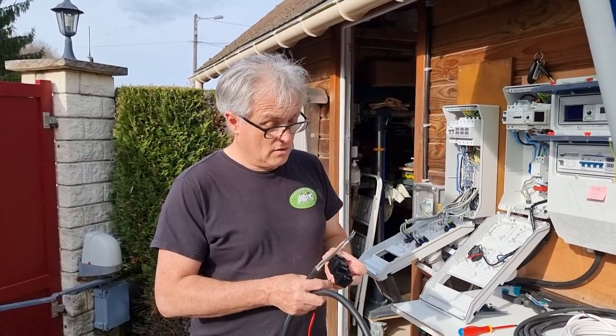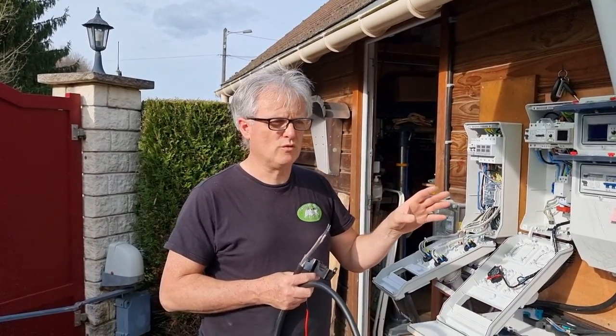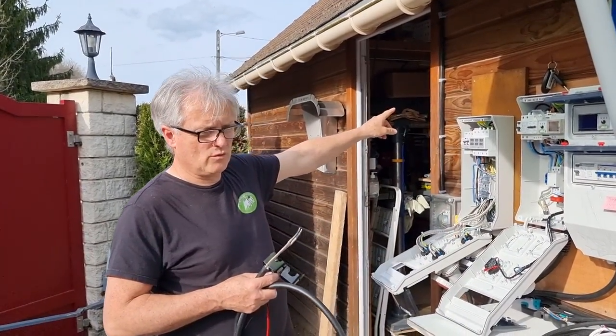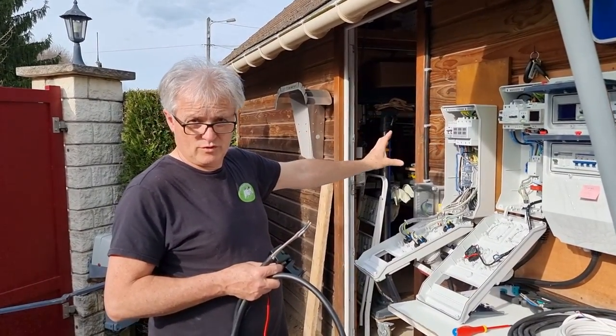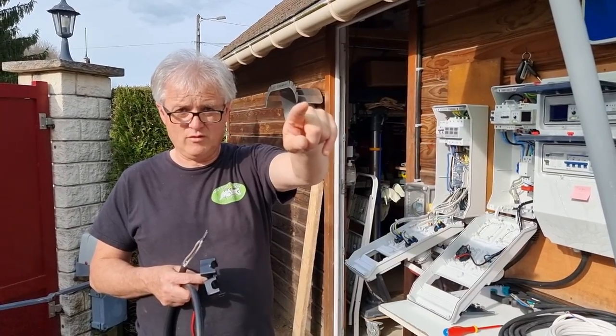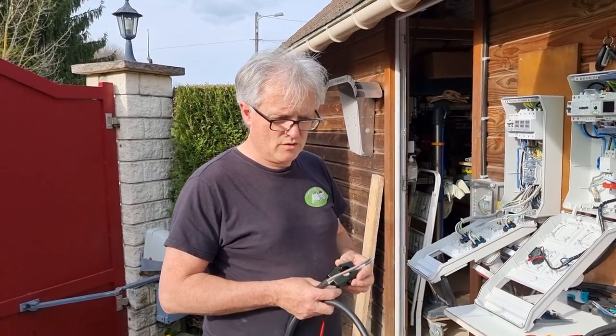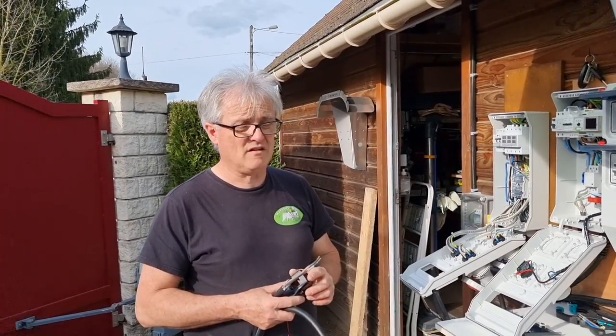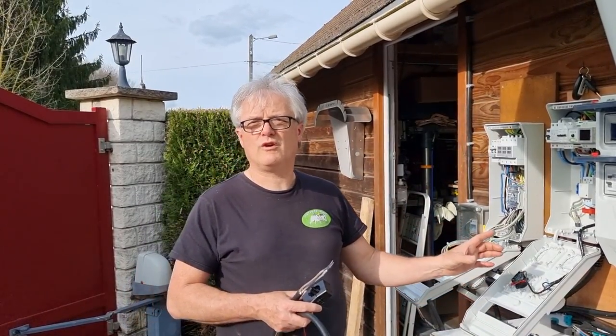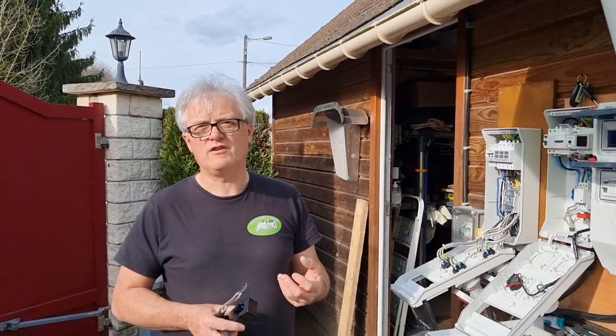C'est des cas extrêmes — 20 mètres du compteur, ça fait beaucoup. Ce n'est pas le compteur qui nous intéresse, c'est le disjoncteur 500 mA. Dans la maison ici, on a le compteur non-Linky en limite de propriété avec un disjoncteur, et un autre disjoncteur qui sauterait avant celui-ci si on tirait trop — ça évite de sortir dehors pour réarmer. Ça veut dire que si le disjoncteur 500 mA est juste à côté du compteur et que le câble qui arrive au tableau électrique est de la bonne section, on peut se prendre directement à l'arrivée du tableau électrique.